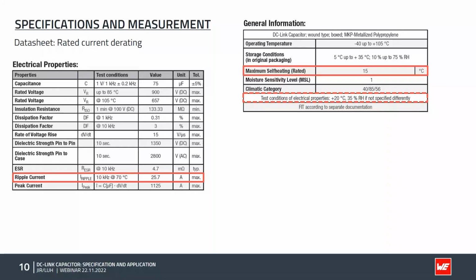So in short, at 70 degrees, with the maximum ripple current specified of 25.7 amps RMS, we expect a self-heating of 15 degrees. With this, we arrive at 85 degrees Celsius, where the rest of the parameters are still valid. As we said before, for temperatures higher than 85 degrees, some specifications must be taken with care because they change.